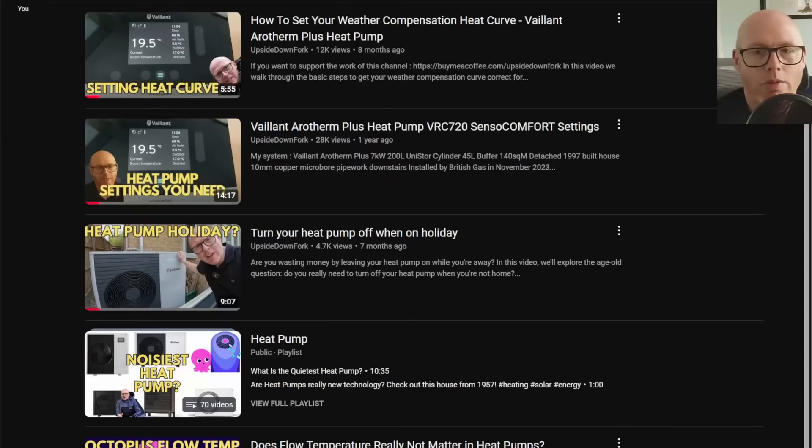But I did a little under six minute video, it's been shared many times on the Facebook owners group and it's helped a lot of people really increase their efficiency. It's really kind of heartwarming to see in the comments people who are really struggling with their efficiency and that just unlocked the key just by reducing their heat curve from 1.2 to 0.6.